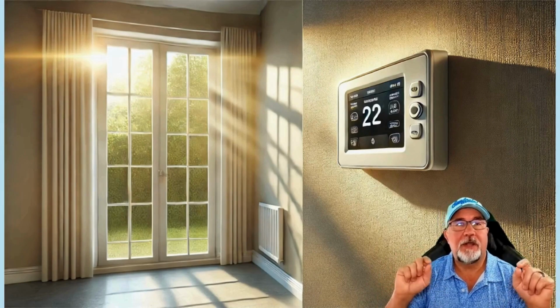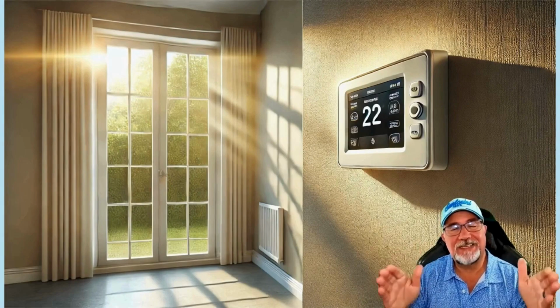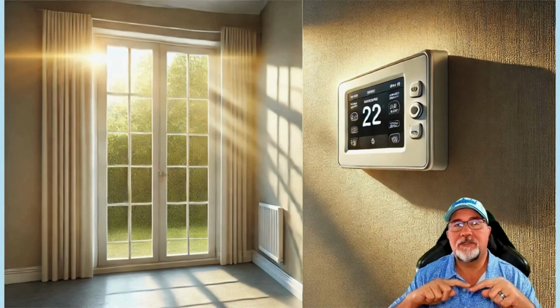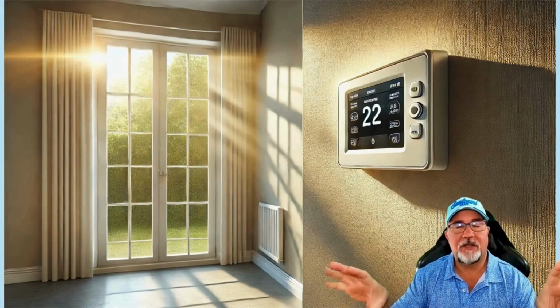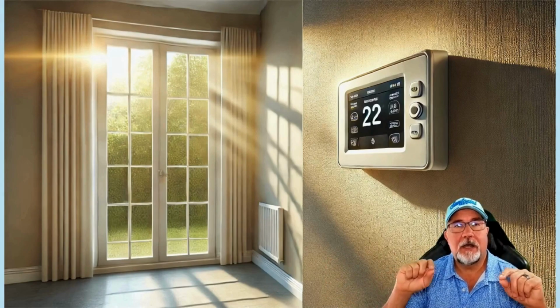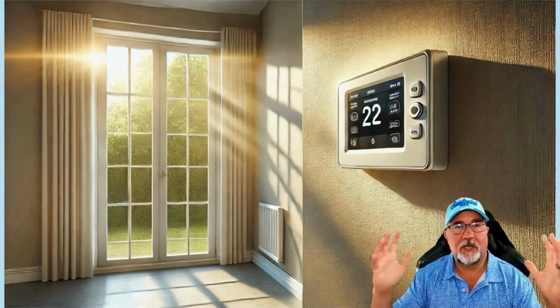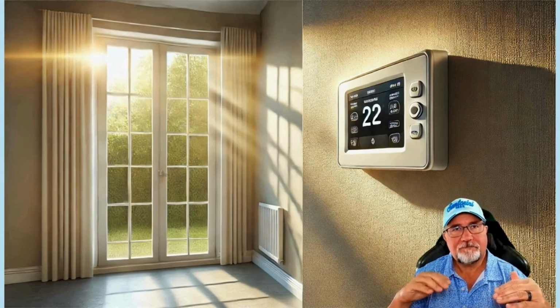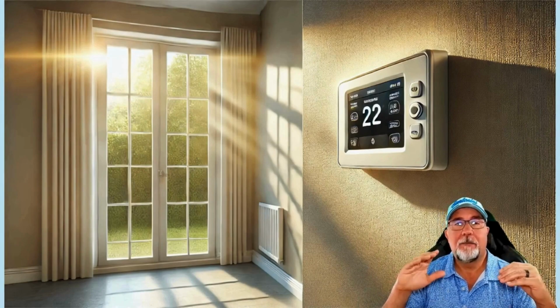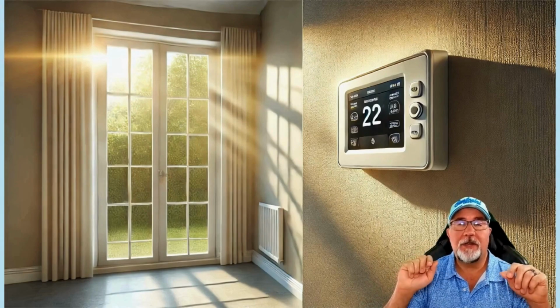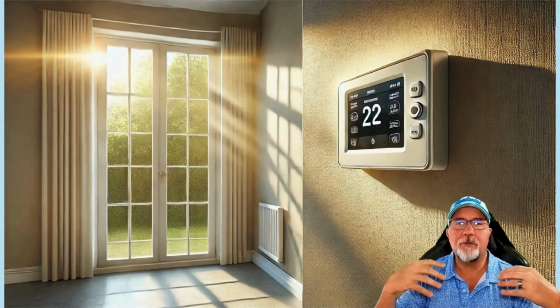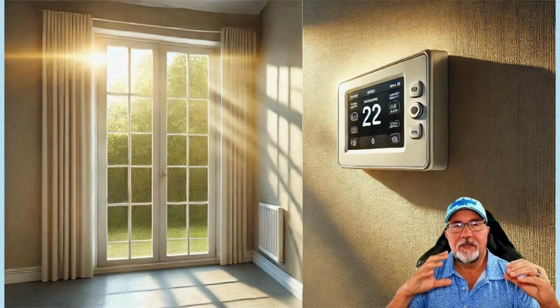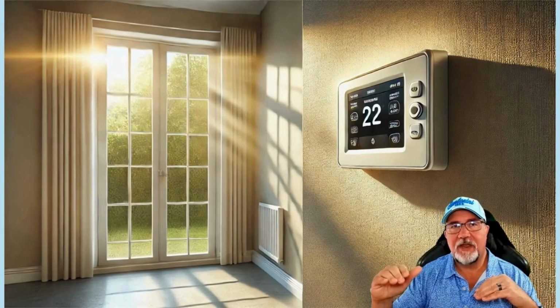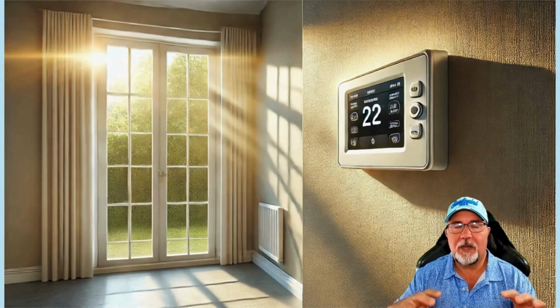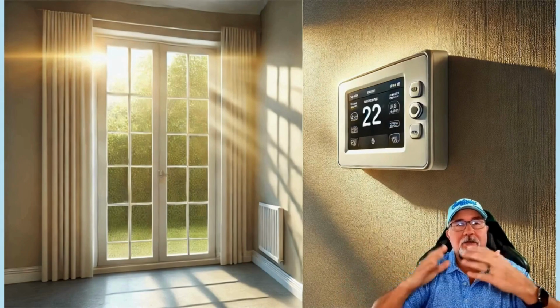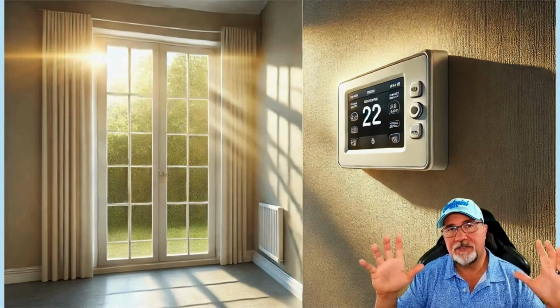So very important that thermostats should be on an inside wall, not a wall adjacent to a garage or any other kind of outside source. It should not be adjacent to any windows where you see sunlight coming in that can affect it. It also should not be in kitchens or by kitchens or by laundry rooms where there's any dramatic heat sources. So very, very important that the HVAC company places it in the right spot so that there's no heat coming from behind it or on the sides of it. Otherwise, it's not going to function properly.